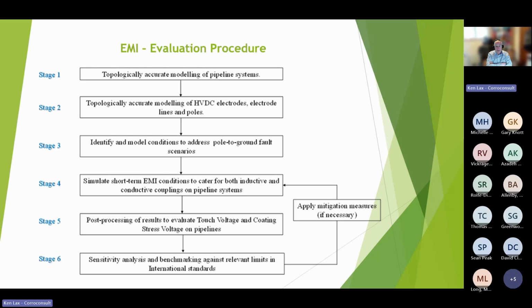But if you get to a point where, under fault conditions or under some conditions, the slope, the voltage gradient, can be so big that it can exceed the stress voltage on the pipeline coating. The proper name for the stress voltage is the dielectric strength, which just tells you how much difference the material can stand on its two faces. And for pipelines, the coatings that we have, which are fantastic for corrosion protection, are not designed to withstand very high voltages. It's just an accident that they do. And a typical coating threshold would be between 2,000 and 3,000 volts. And it will withstand that reasonably well any number of times.